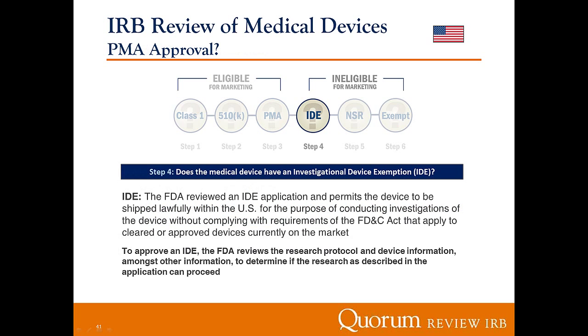Now moving on to that second part of the linear step line. So if the device isn't Class 1, doesn't have a 510K, doesn't have a PMA, so it's not eligible for marketing, well, it still can be used in a clinical trial, but it's going to require an investigational device exemption. So it's going to require submitting an application to the FDA so that the FDA can say, yes, it's permissible for you to use your device in a clinical trial, even though we haven't approved it or cleared it. It can be shipped through interstate commerce, and that's acceptable. So to approve an IDE, what the FDA is looking at is it's reviewing the research protocol and device information, amongst other information, to determine if the research as described in the application can proceed.